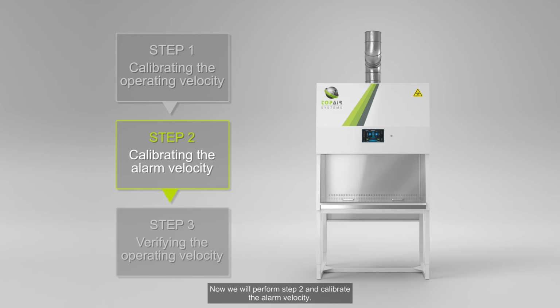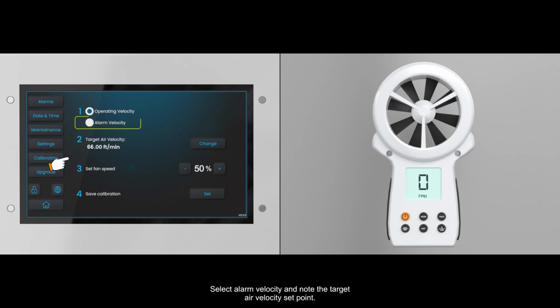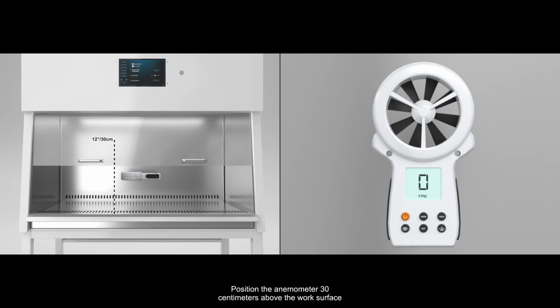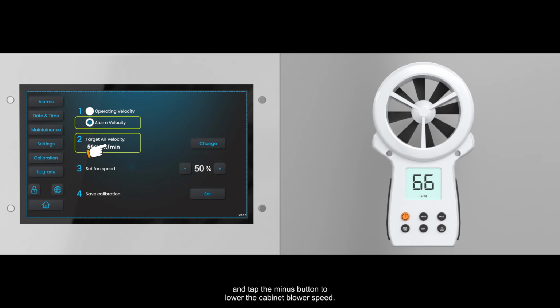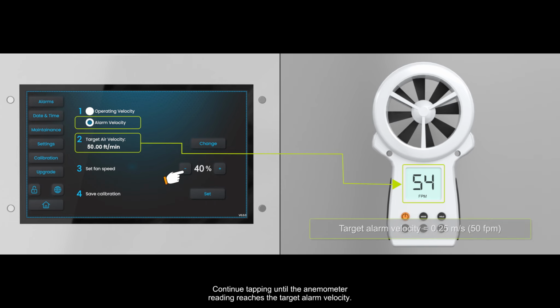Now we will perform Step 2 and calibrate the alarm velocity. Repeat the same calibration process for the alarm velocity. Select alarm velocity and note the target air velocity set point. Position the anemometer 30 centimeters above the work surface and tap the minus button to lower the cabinet blower speed. Continue tapping until the anemometer reading reaches the target alarm velocity.